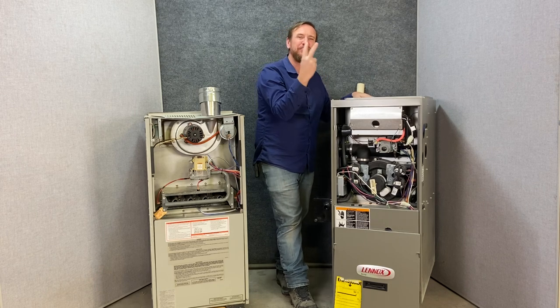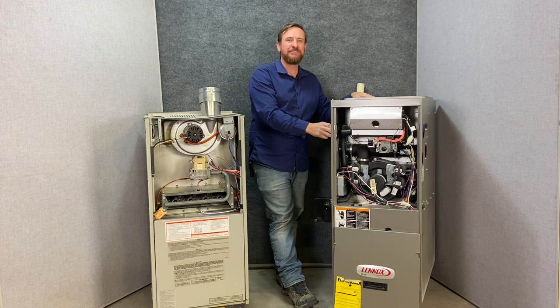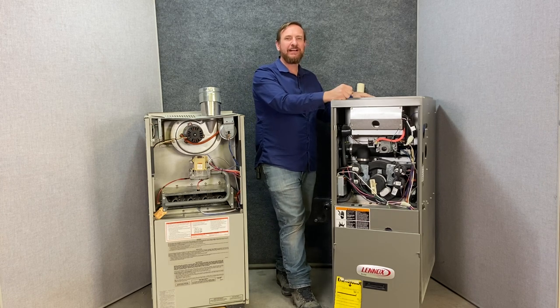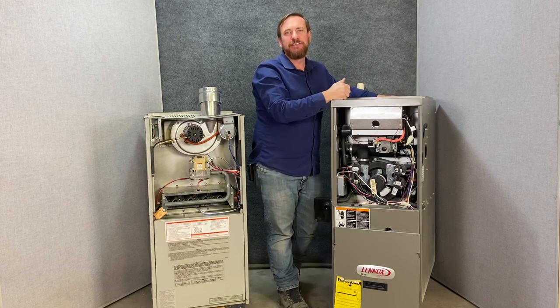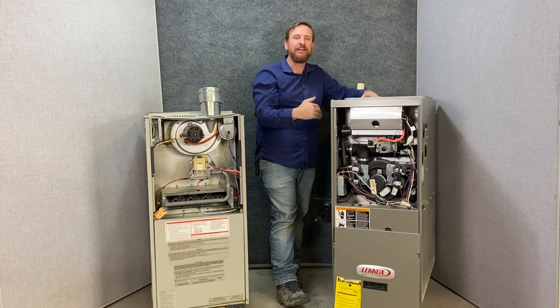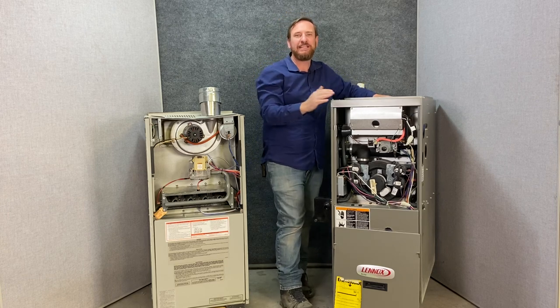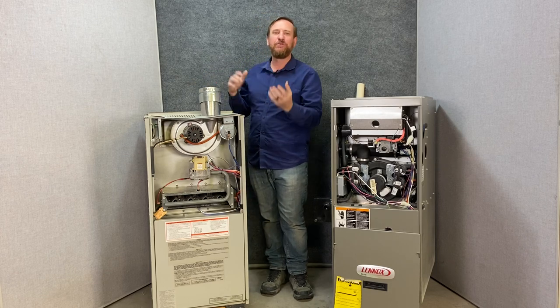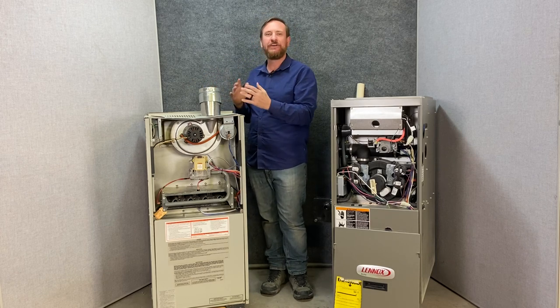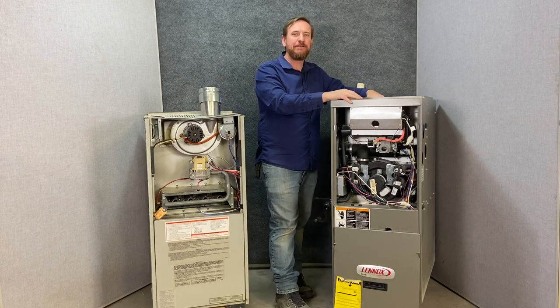What's also cool is this furnace is a two-stage gas furnace. It's also a 45,000 BTU input on low fire with 43,000 BTU going to heat the house. In the spring and fall when you need heating but not massive amounts, we can run on low fire — heat the house, have longer run times, and have less temperature swing. Instead of the furnace coming on, heating all at once, the house getting warm then cooling off on and off, this furnace runs on a lower setting, nice and continuous, giving you an even amount of heat.